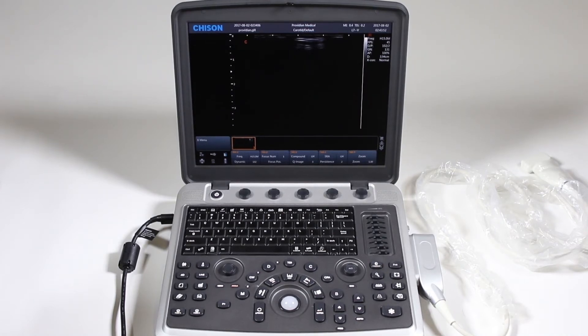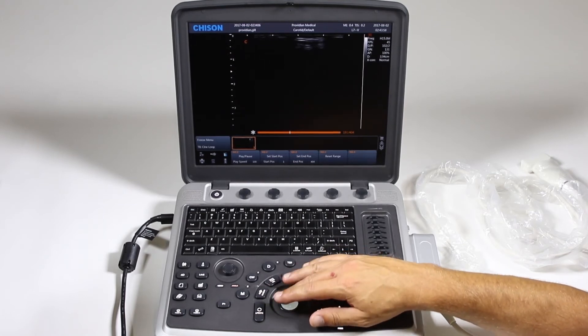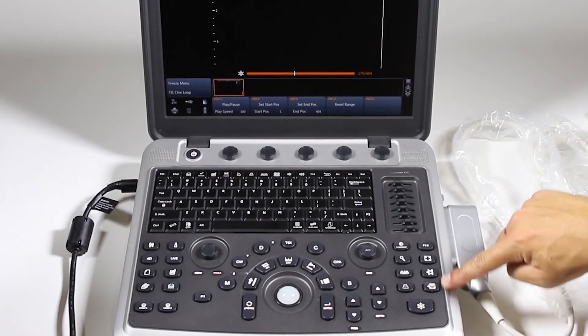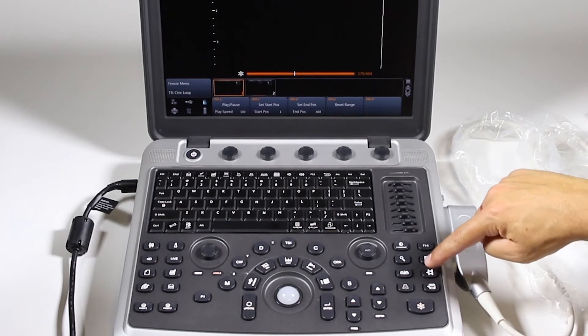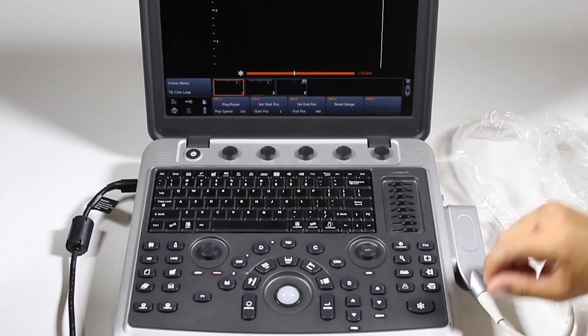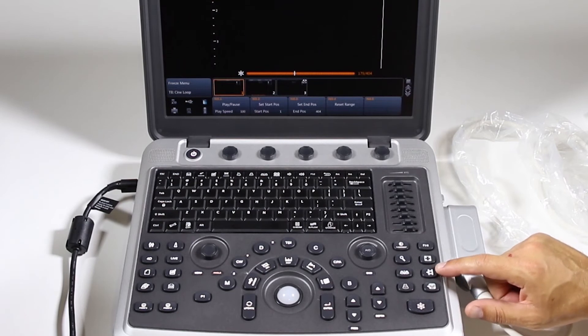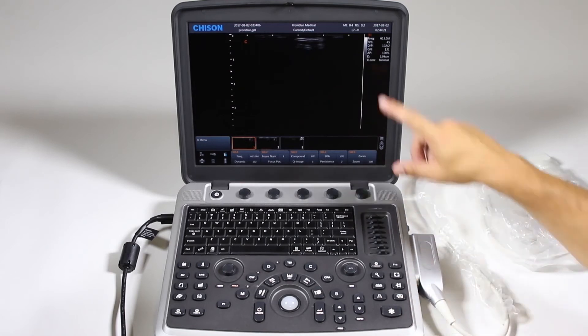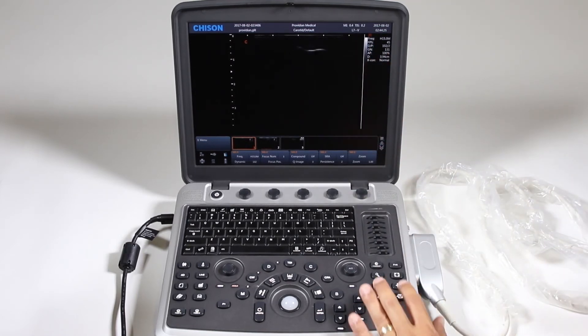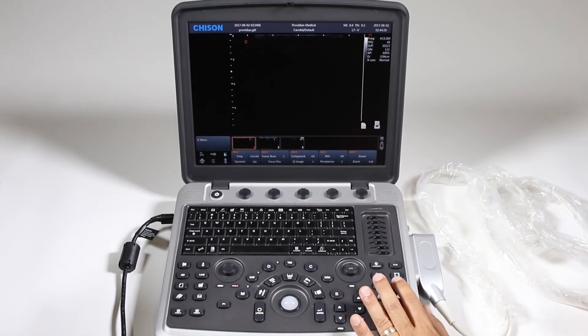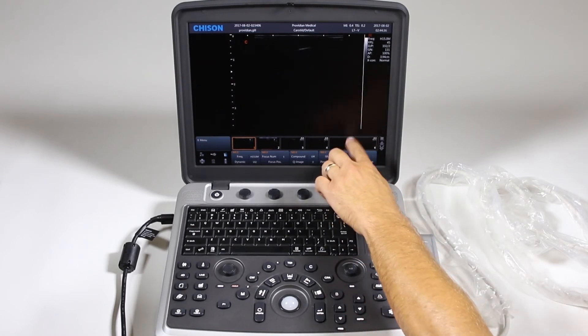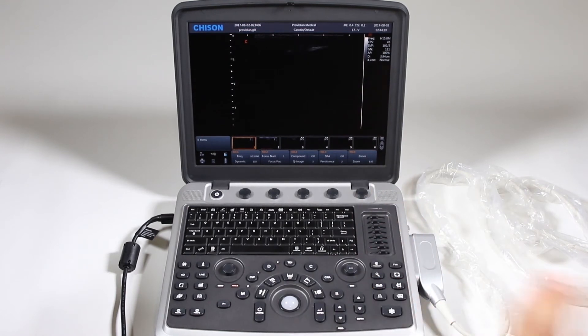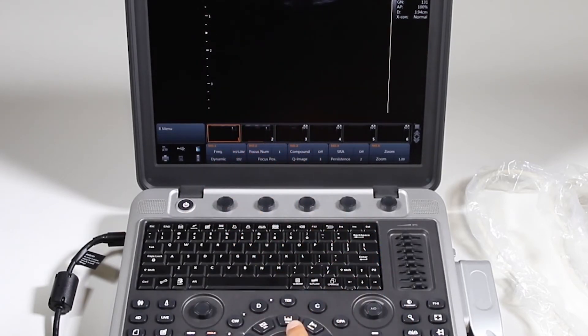To freeze and save an image, you're going to freeze here. You can use this Cine scroll bar to go to a certain point in the image. Say you want to save that, just click this. This is to save a still image. This little disk button here. This one that looks like a film strip saves a Cine loop. If you notice how fast that is, that saved 404 frames very, very quickly. And that's pretty unique for this machine. You can save a loop prospectively or retrospectively. Meaning, if I unfreeze and I want to save the live image while I'm recording, I can just hit this button and it's going to continue saving. And you can choose a certain length in the beginning or you just hit start and stop. And it will save that loop. And those loops are indicated by like a little film canister right there. So you know which ones are loops and which ones are not. You'll see here these are stills. They do not have a little film canister. So that's just a static image.